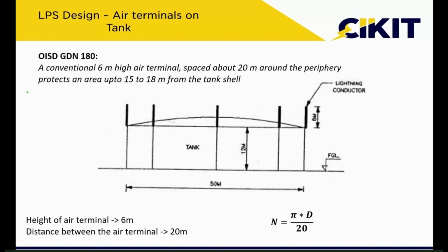So the first methodology is placing air terminals on the tank itself. Here they have mentioned that we can directly place the air terminal on the tank wall itself. OISD GDN 180 has highlighted that 6-meter high conventional air terminals can be used around the perimeter of the tank, and one more thing is we have to place them at a distance of around 20 meters. So at every 20 meters we have to place one air terminal. Since this is a circle, the perimeter will be pi d, or 2 pi r, for this particular tank.